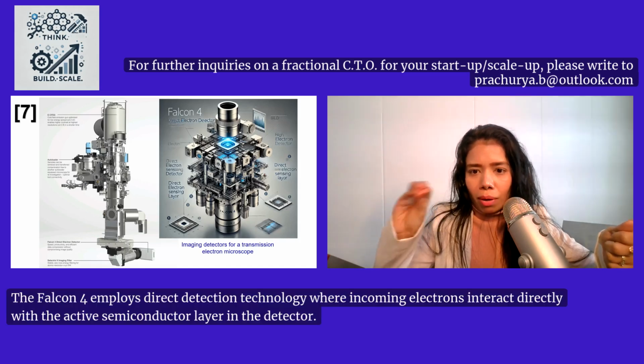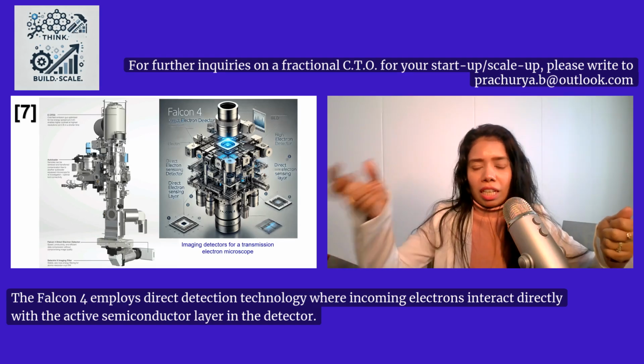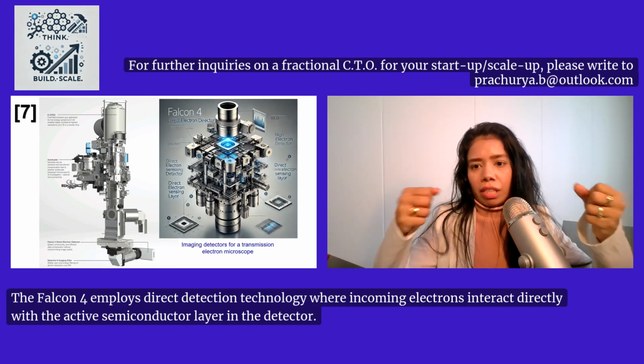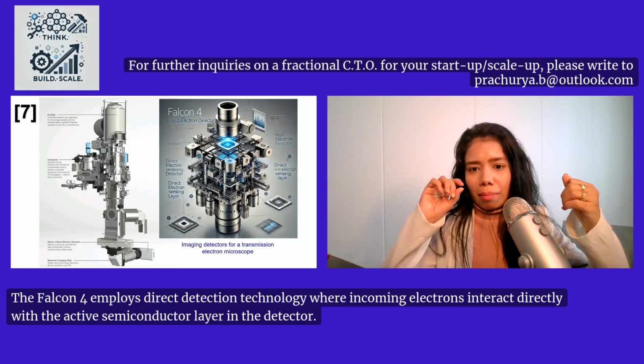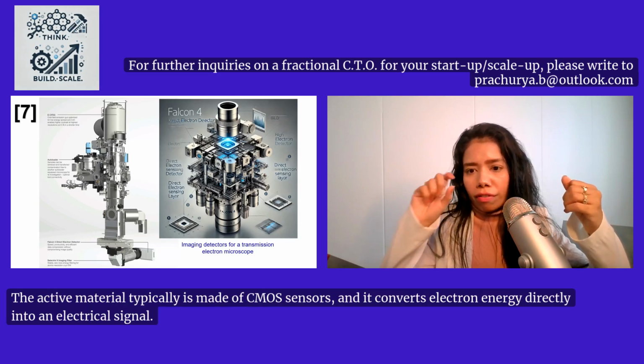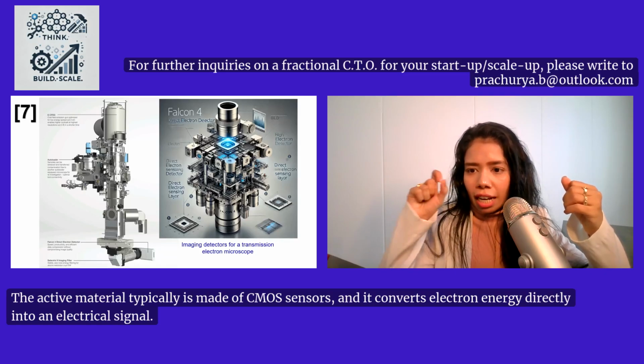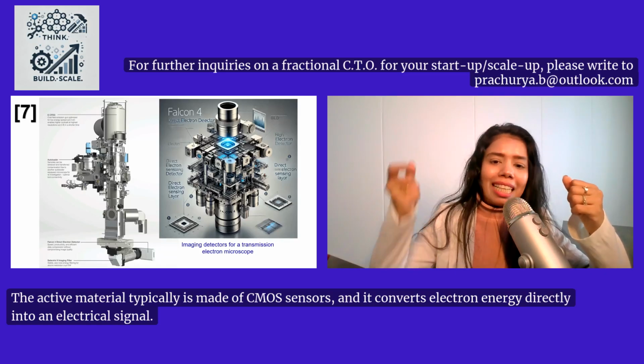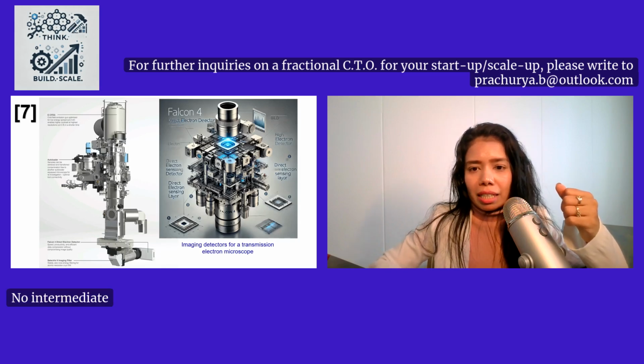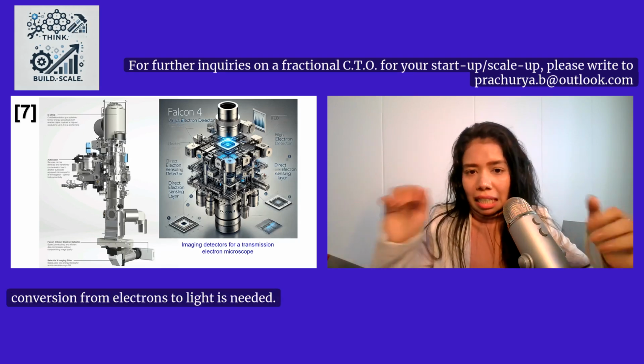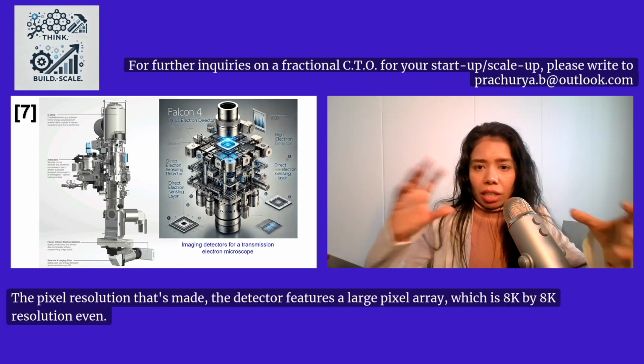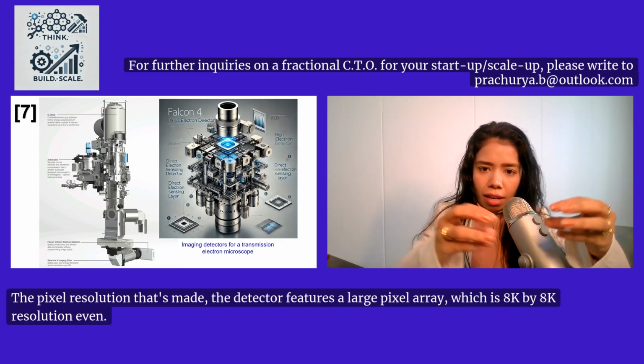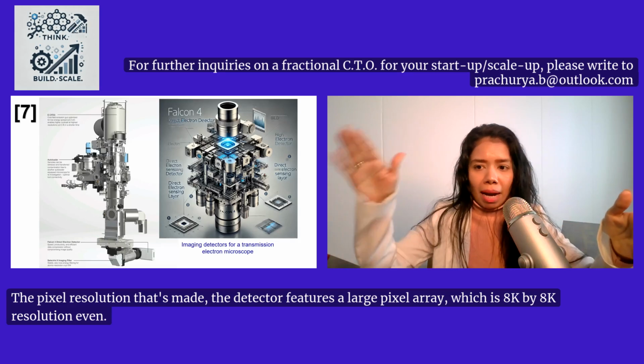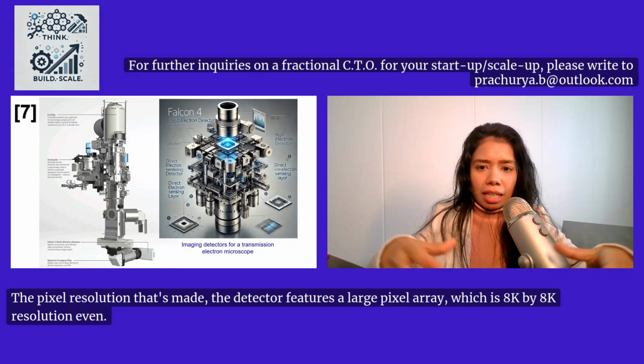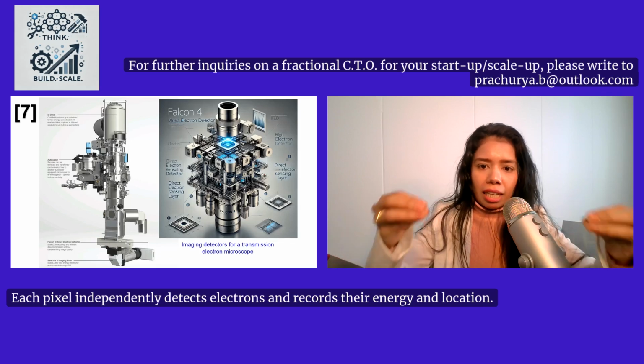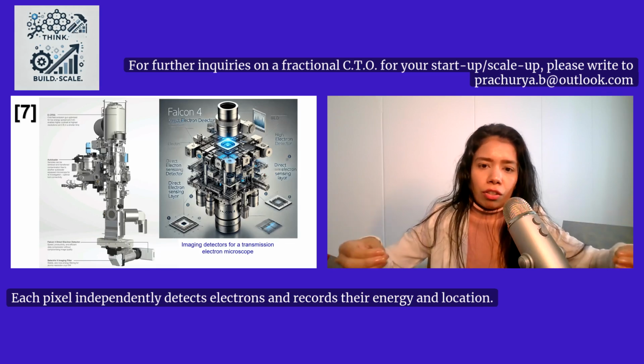The Falcon 4 employs direct detection technology where incoming electrons interact directly with the active semiconductor layer in the detector. The active material typically is made of CMOS sensors, and it converts electron energy directly into an electrical signal. No intermediate conversion from electrons to light is needed, and that's an advantage. The pixel resolution: the detector features a large pixel array, which is 8K by 8K resolution even. Each pixel independently detects electrons and records their energy and location.